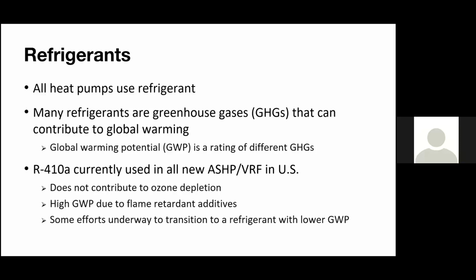The one thing is that once we start using these HFCs, they have more hydrogen atoms, and they tend to be a little bit more flammable. So what we do is combine them with some sort of flame suppressant in order to make them less flammable and safer to use. And that increases what we call the global warming potential, or GWP.